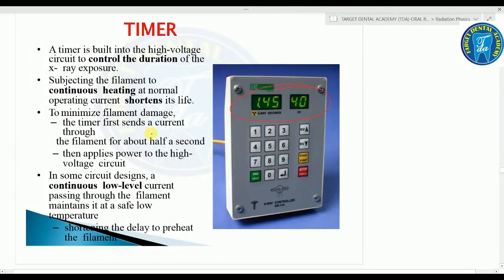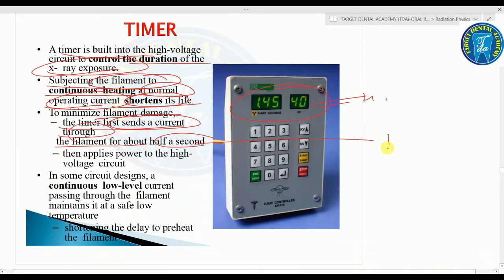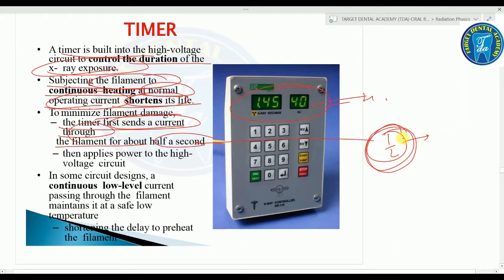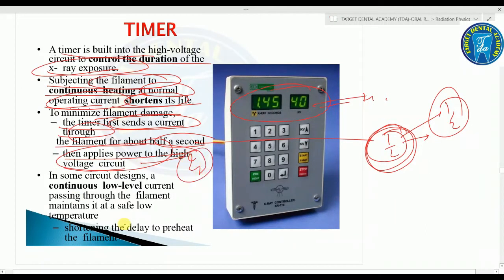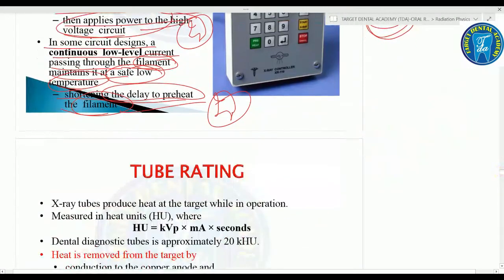The timer is built into the high voltage circuit to control the duration of X-ray exposure. Continuous heating of the filament shortens its life. To minimize filament damage, the timer first sends current through the filament for about half a second to preheat it, then applies power to the high voltage circuit. In some circuit designs, a continuous low-level current passes through the filament, maintaining a safe low temperature and shortening the preheat delay.